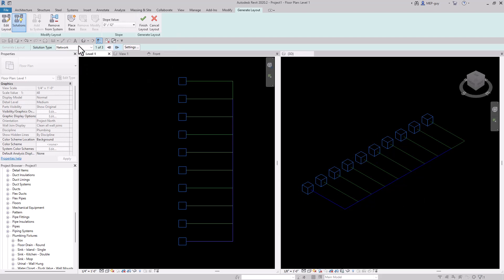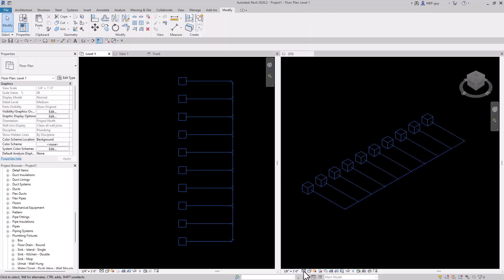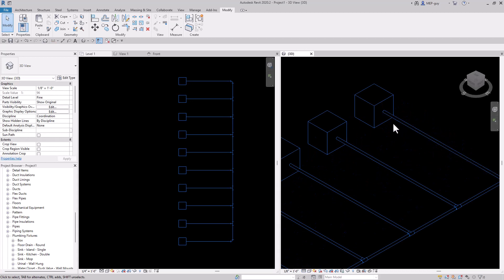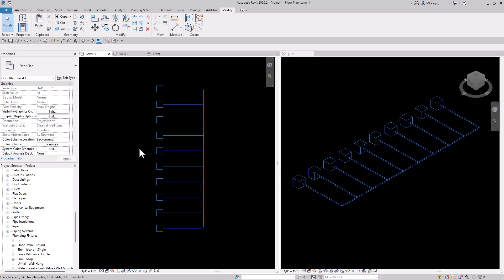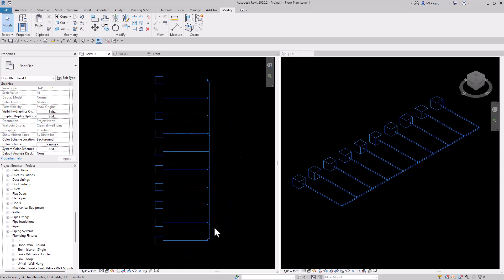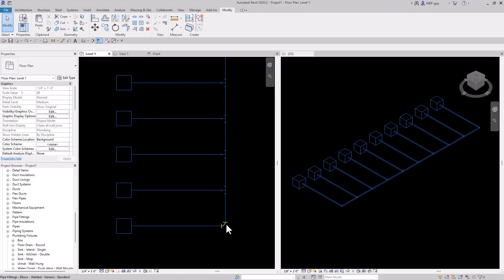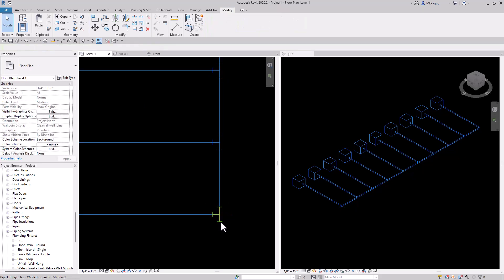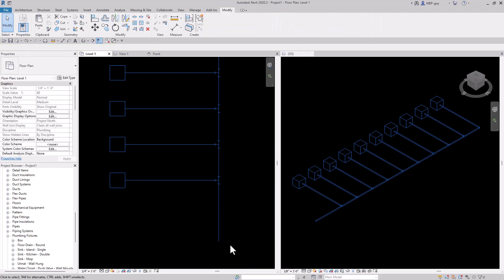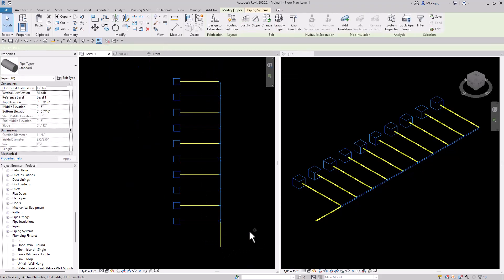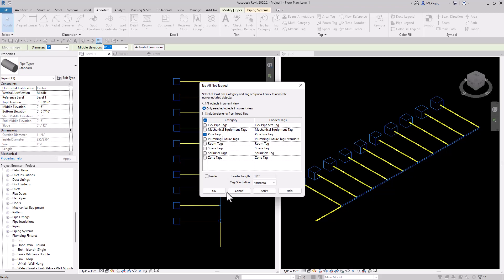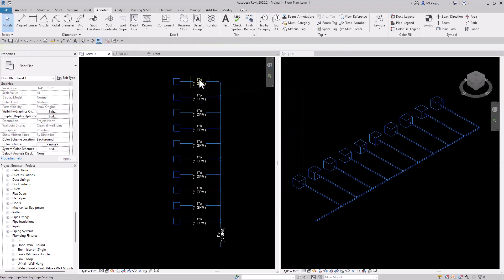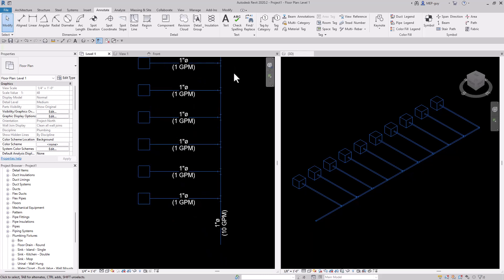I'm just going to finish the layout and change our view to fine. You can see we're using a one inch piece of pipe into our box connecting to our little connectors. Let's tag this floor plan — I'll draw some more pipe down this way, then select the pipes and go to annotate, tag all, using this pipe tag I've created. The pipe tag shows diameter and GPM — each one is one GPM, and 10 GPM is entering our system.